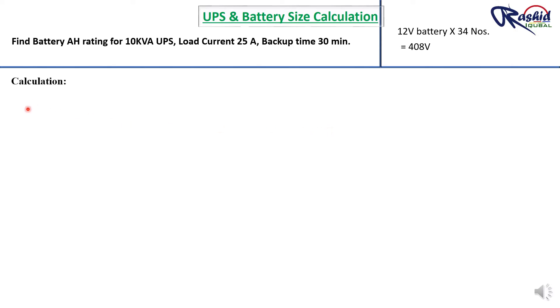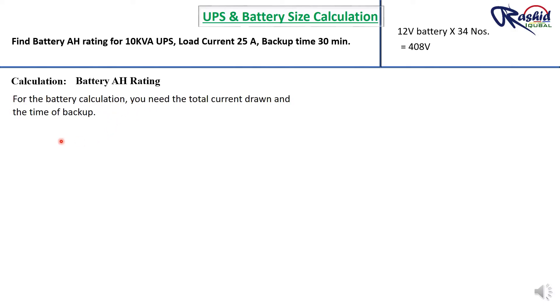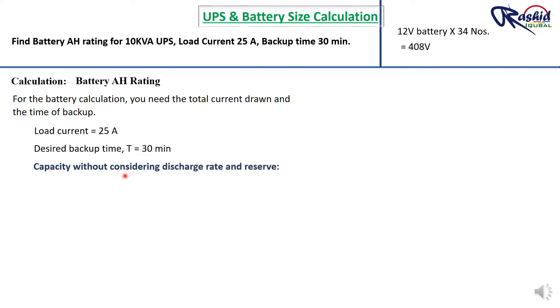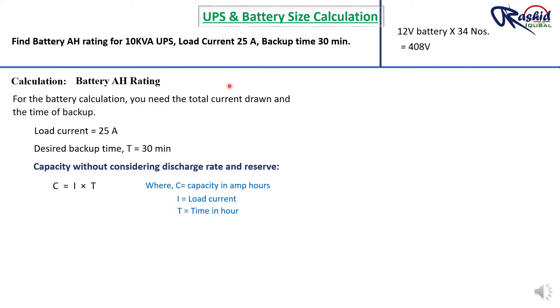Let's start the battery AH rating calculation. For battery calculation you need total current drawn and backup time. Load current I = 25 A, desired backup time T = 30 minutes = 0.5 hours. The basic formula is C = I × T, where C is battery capacity in ampere-hours. So C = 25 × 0.5 = 12.5 AH.